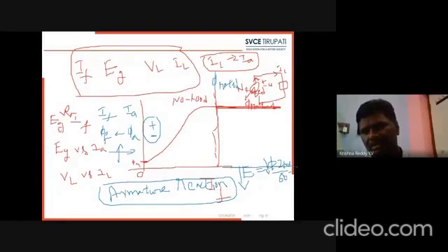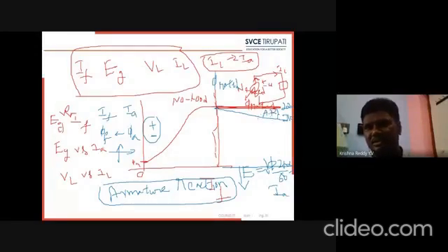Here we keep on increasing the armature current. As the armature current increases, the armature flux distortion will increase. Initially there is no distortion, we have rated flux, and we get rated voltage. As the armature current increases, the flux distortion increases, and the armature reaction increases. Now the voltage decreases from 220 volts to 210 volts. This drop occurs due to the armature reaction. These are the characteristics of Ea versus Ia.